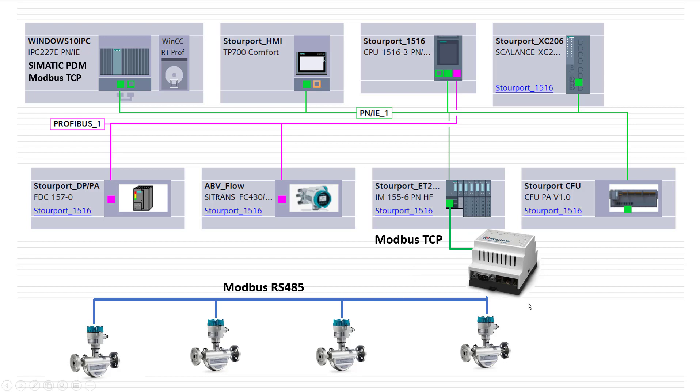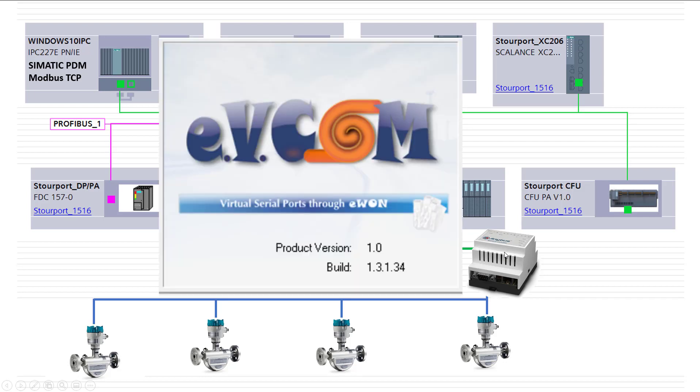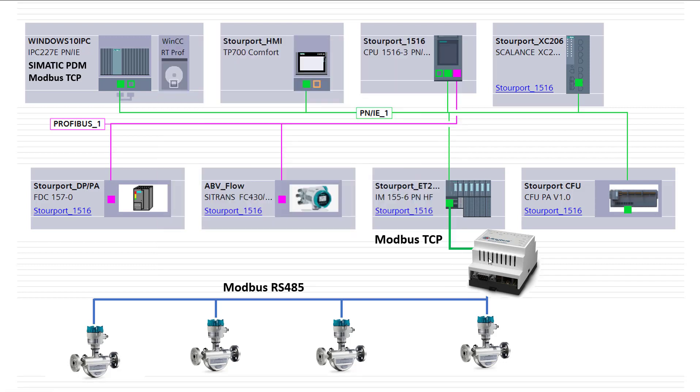So it's really flexible, and what we're going to do over the next two videos—I'm going to show you how to set this up, because the beauty of this HMS device, it comes with a virtual port replicator because SIMATIC PDM at the moment doesn't support Modbus TCP connectivity. But this port replicator will take the IP address and the settings for this device and make it look like a standard USB COM port adapter. So as far as PDM is concerned, it's connecting to a Modbus 485 network; it's not connecting to a Modbus TCP.